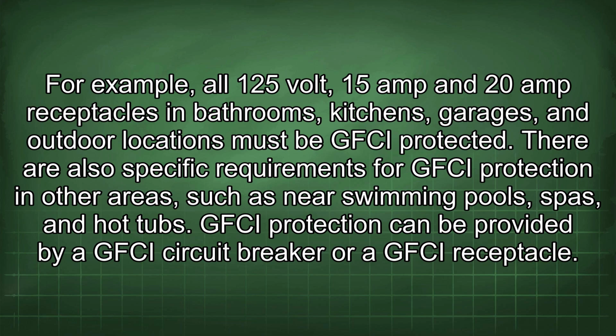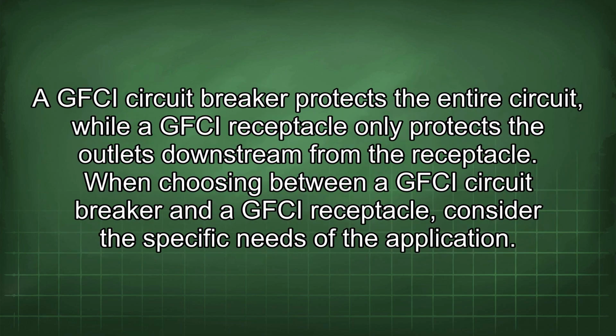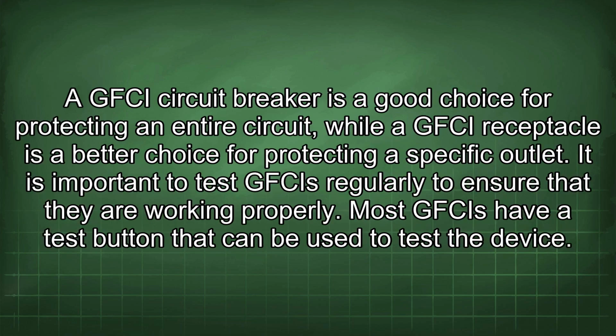GFCI protection can be provided by a GFCI circuit breaker or a GFCI receptacle. A GFCI circuit breaker protects the entire circuit, while a GFCI receptacle only protects the outlets downstream from the receptacle. When choosing between a GFCI circuit breaker and a GFCI receptacle, consider the specific needs of the application. A GFCI circuit breaker is a good choice for protecting an entire circuit, while a GFCI receptacle is a better choice for protecting a specific outlet.